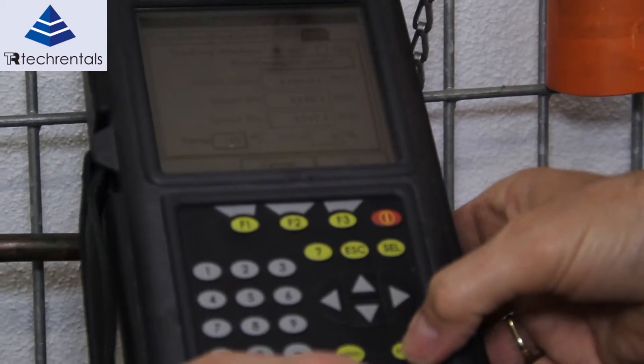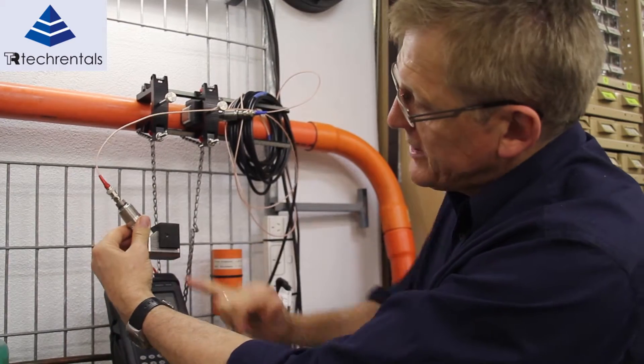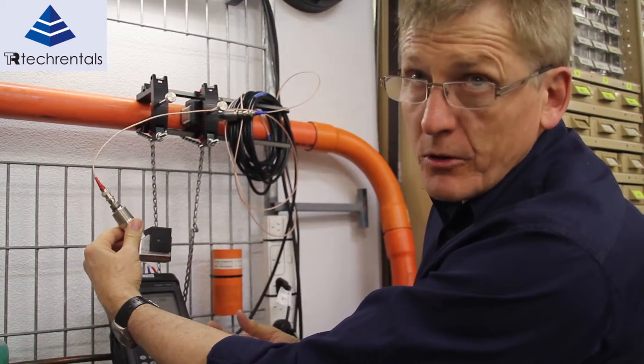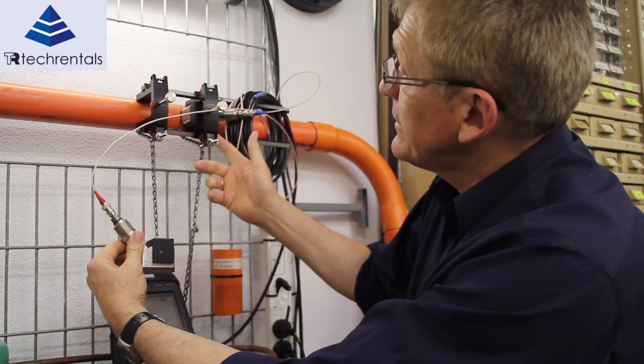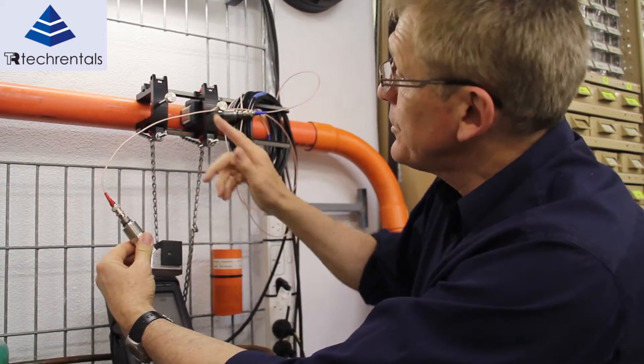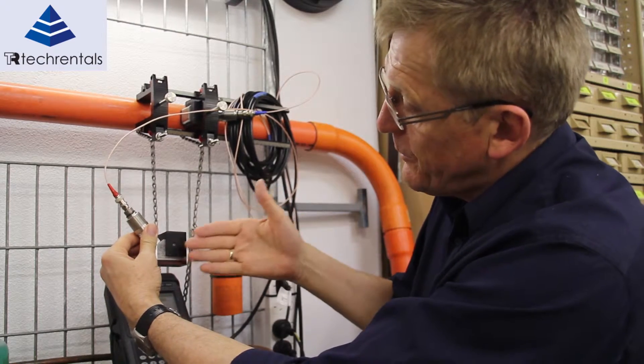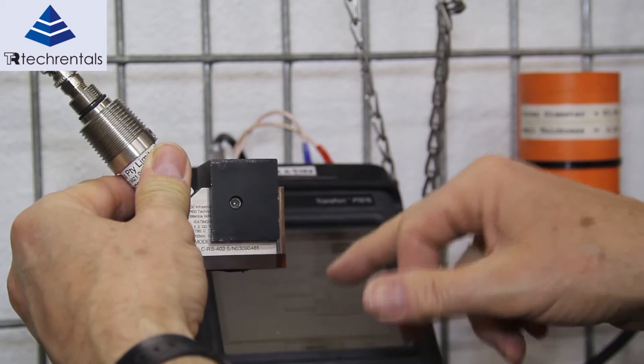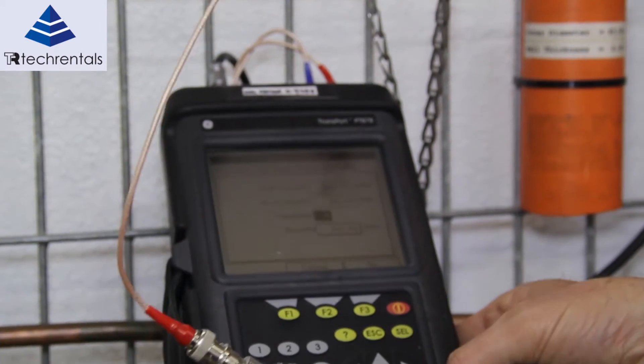Last thing we need to do is select the number of paths. If we have a single path, here's the pipe here, that means we'd have the transducers on opposite sides. This particular jig is configured for two paths, however if we use two paths we'll end up with the transducers so close together they'll be hitting each other. So in this instance we'd select 4, usually this would be 2.